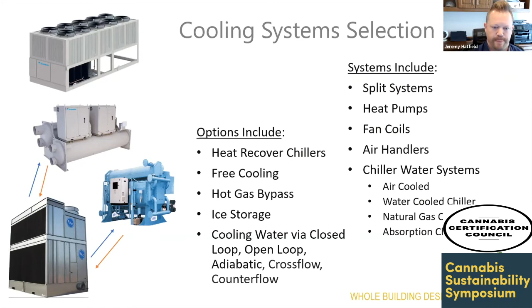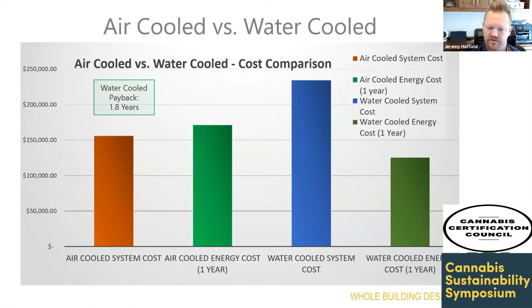We ran two parallel designs, one air cooled and one water cooled, to show the difference between the systems. No surprise to any mechanical designer, the air cooled system cost was quite a bit lower than the water cooled system, but its energy costs were quite a bit higher. We came up with a 1.8 year payback to go water cooled.